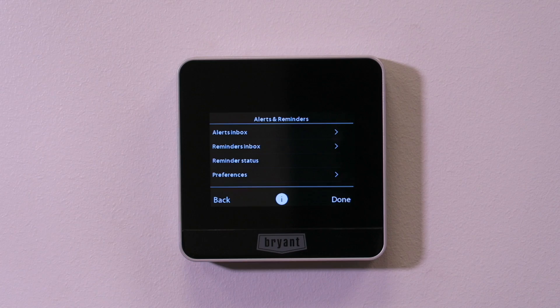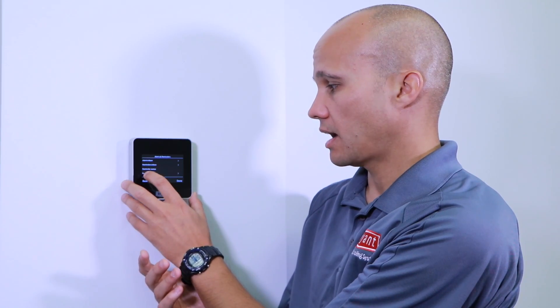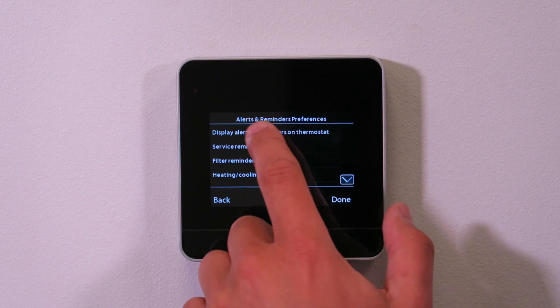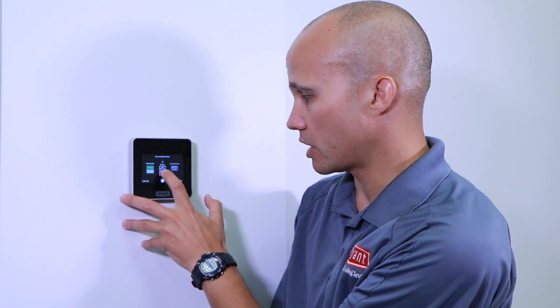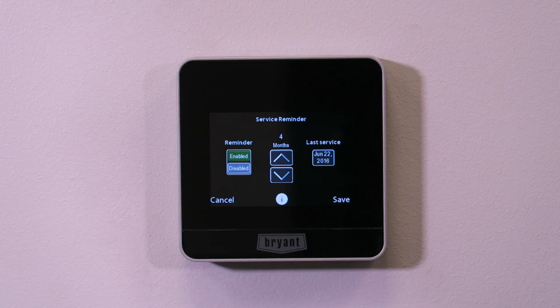Next I'm going to look at the alerts screen. There's an inbox for any alert messages — I don't have any because the stat is brand new — and reminders like filter changes, but nothing yet. Under preferences, I can set display alerts or reminders on the thermostat; normally you'd leave that on, but you can disable it if the customer finds it annoying. Service reminder: when do you want to next service this system? If I installed it in June, I might set a reminder for four months out in October to do a heating safety check before the fall season — and the customer will automatically get a reminder.